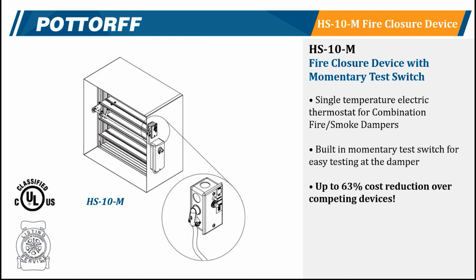So if this is just a simple test switch where you want to be able to open and close the damper and you don't need a signal back to a building management system, you can use this. Of course, if you're using a smoke control system or the engineer does call out position indication switches, we always recommend using a PI50 and factory ordering that, since retrofitting is a tough option. But you can additionally use auxiliary switches in the actuator for that on a separate signal.